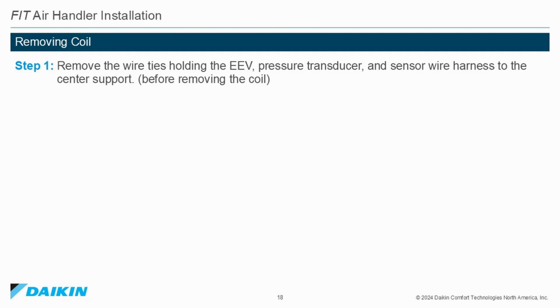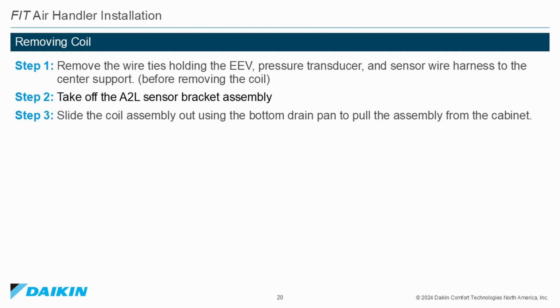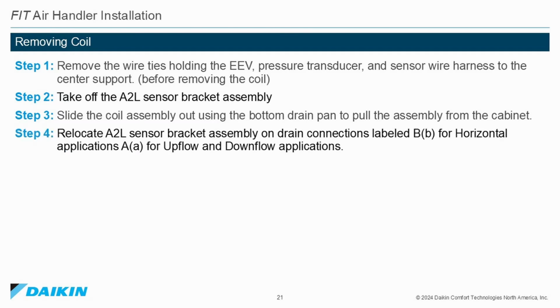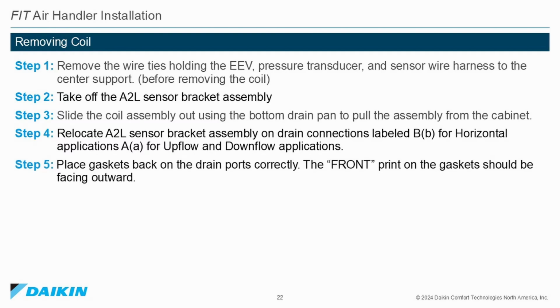Removing the coil. Step 1. Remove the wire ties holding the EEV, pressure transducer, and sensor wire harness to the center support before removing the coil. Step 2. Take off the A2L sensor bracket assembly. Step 3. Slide the coil assembly out using the bottom drain pan to pull the assembly from the cabinet. Step 4. Relocate the A2L sensor bracket assembly on the drain connections labeled B for horizontal applications and A for upflow/downflow applications. Step 5. Place the gaskets back on the drain ports correctly.